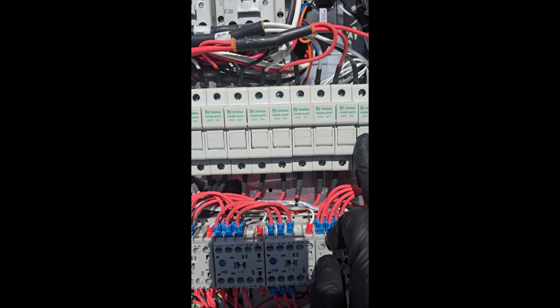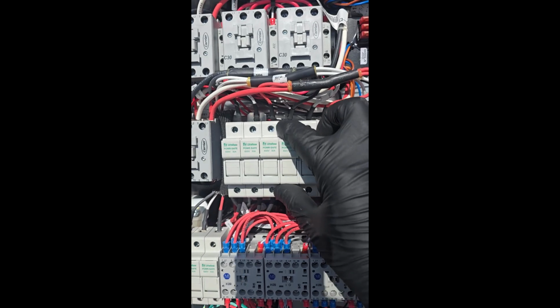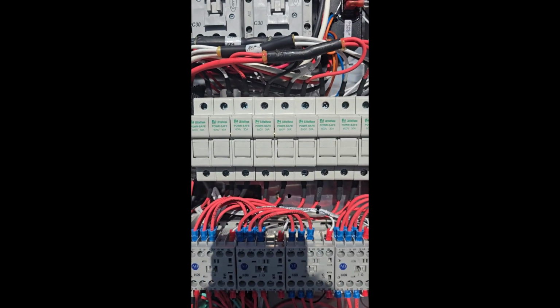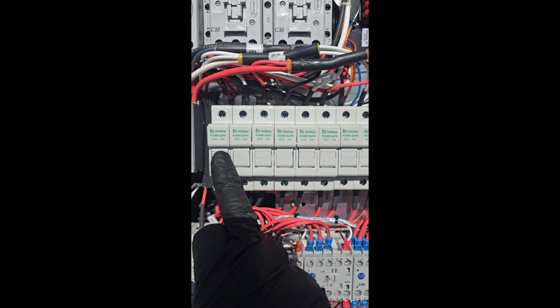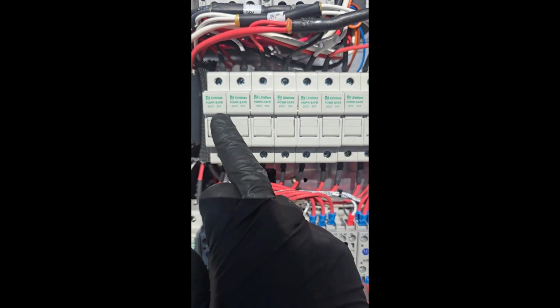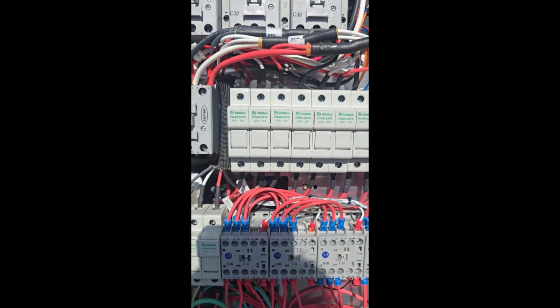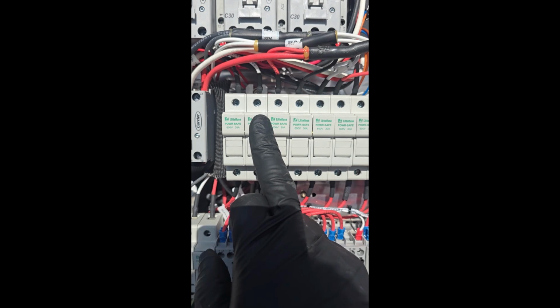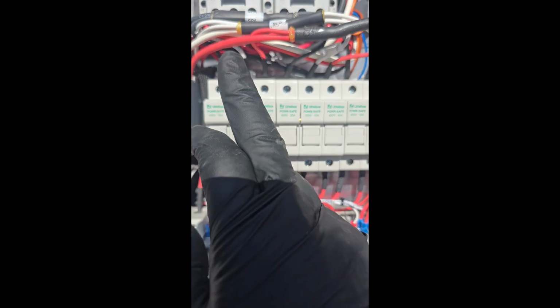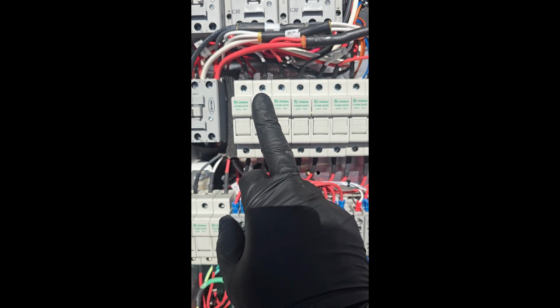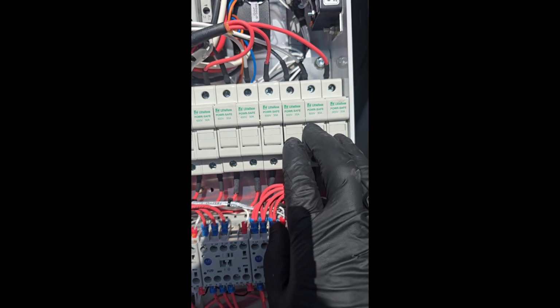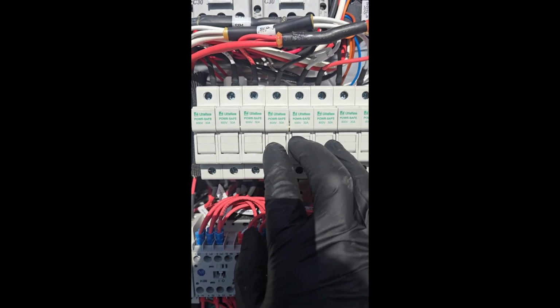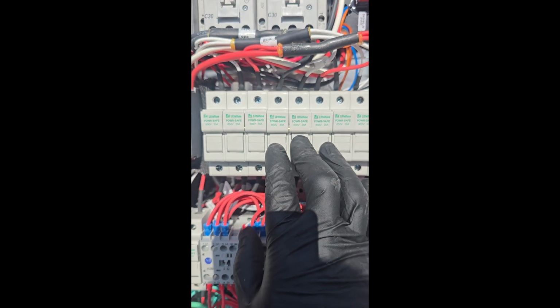One other thing I didn't go over, something you should just do, is check your timed fuses—check continuity with your meter across here with ohms, and you should have resistance. This has two compartments, so these fuses here, in the second compartment, will have fuses in it. Some units will, some won't. If there's no second compartment, there will be no time fuses in here; if there is a second compartment, don't remove them. But you have your heater strips here, your battery charger here, and then your 3 fan fuses here, tied to all 3 fans—the 2 condenser fans and the evaporator fan circuit, 1 per leg.